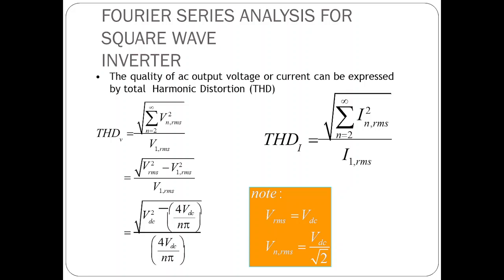So the total harmonic distortion is the parameter that tells us whether the inverter is operating properly or with good efficiency. Why? Because if THD is calculated, we can know what percentage of the current is not in a proper form, and therefore how the total harmonic distortion affects performance. If the total harmonic distortion is less, like 4% or 5%, then it is a good standard.